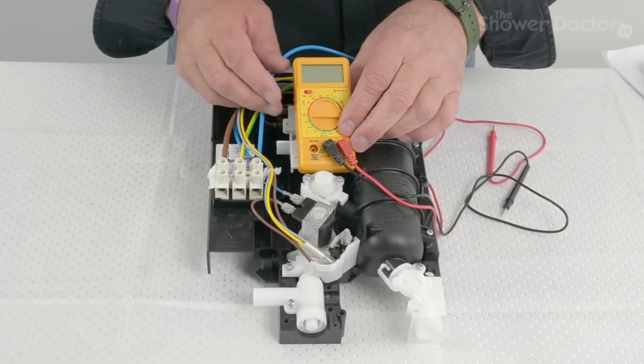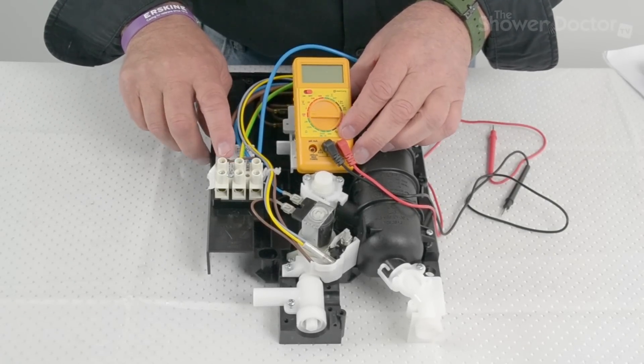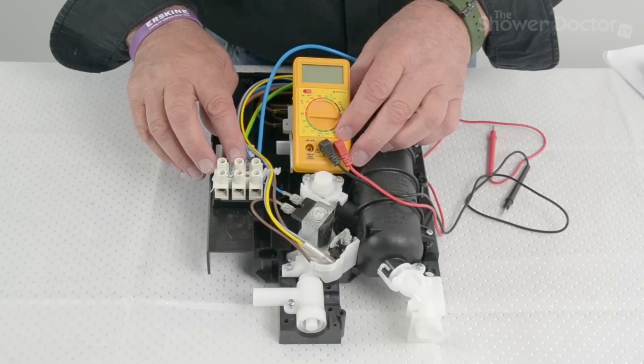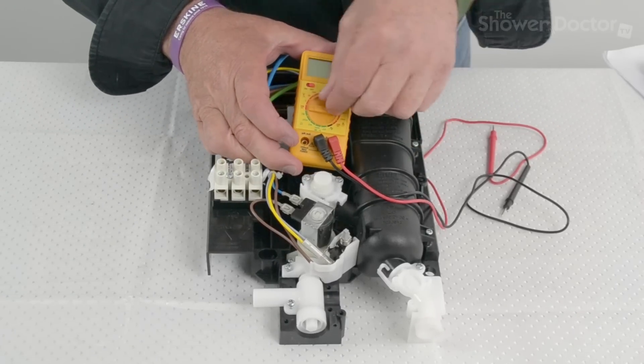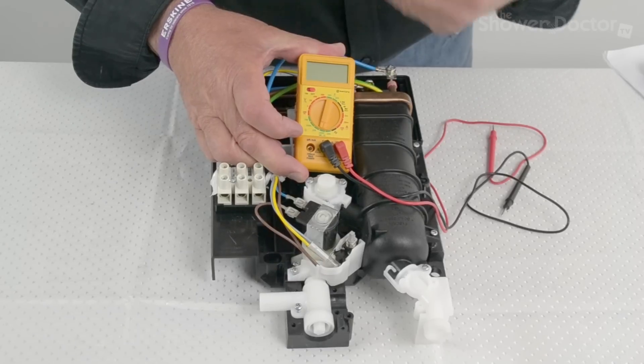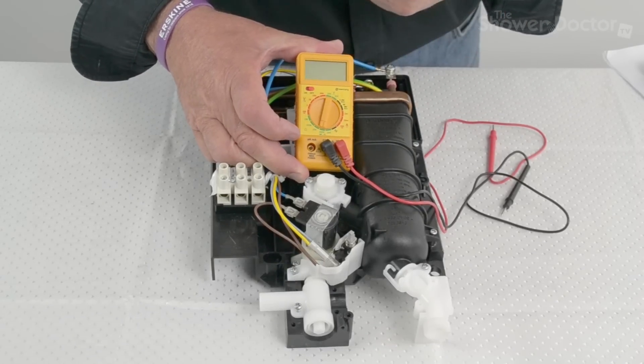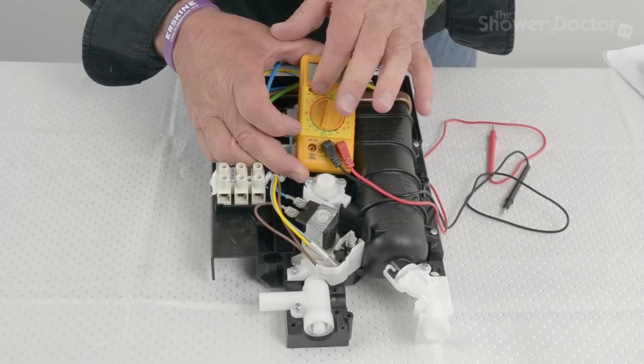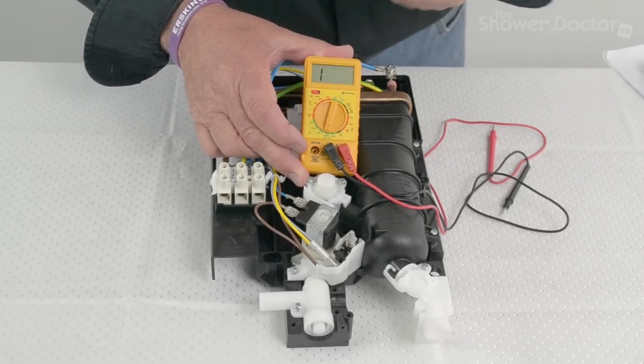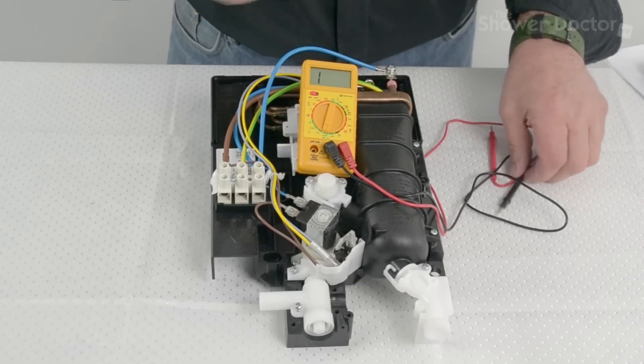Now we're going to do some continuity checks. We know that there's power getting into the unit we've switched off again to make sure it's safe and we're going to check continuity. So with our meter we need to set it down here to the continuity. Now if it has continuity the meter will bleep and when it bleeps we know that the continuity is there. The bleep is quite quiet so you may have to listen carefully to hear it but here we go.